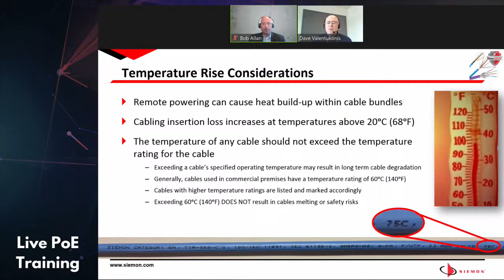Now, you also don't want to exceed the jacket rating of a cable. We're not talking about a situation where cables are going to spontaneously combust or melt or anything. As entertaining as that might be, it doesn't sound like the safety things that Bob would like to see in an intelligent building. It's really that if you're going above the rating consistently, you're going to degrade the cable beyond its expected lifespan. So we want to make sure you don't exceed 60 degrees C, which is about 140 degrees Fahrenheit. That's what cables are typically rated to, but you're seeing more constructions come out with higher jacket ratings, for example 75 degrees C, to address this heat buildup.